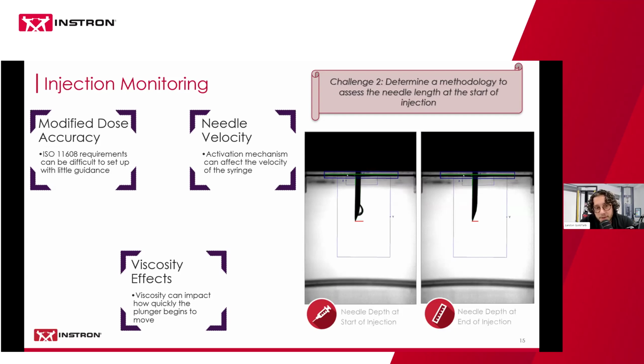It brought up the concept of modified dose accuracy, which essentially says you need to ensure that your drug is delivered solely within the therapeutic range, whether that's 4 to 8 millimeters of needle depth, whatever it might be for your specific combination product. It's just ensuring that.